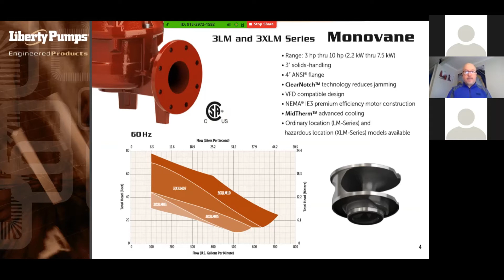another style. Sometimes we get asked, well, why do you use one over the other? The enclosed 2-vane, we really put in the offering for situations where maybe another manufacturer was specified and it was a 2-vane, and for whatever reason, maybe an engineer is not going to get convinced to switch it to a mono vane. He wants to definitely go with a 2-vane, and that's fine. We just have it in the offering for that type of reason. Ideally, the mono vane is a more efficient design, and we've found in our testing that the mono vane passes the occasional wipe and rag better because it's one less leading edge for that to grab onto and cause it to start wadding up.